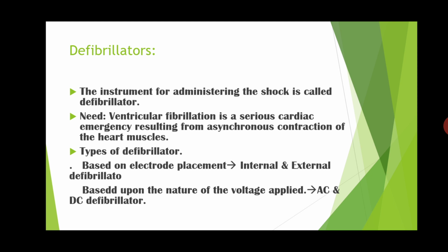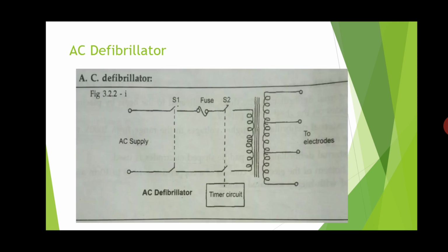Now the types of defibrillator based on the nature of the voltage applied. That is an AC defibrillator and a DC defibrillator. So first we will see the AC defibrillator. This one is the diagram for the AC defibrillator. In this they are using the step up transformer.